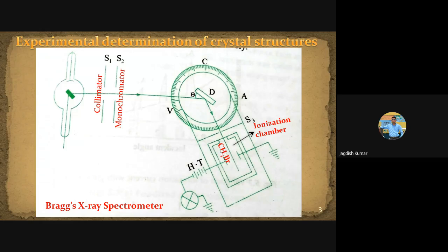So you will have CH3 plus ions and bromine negative ions, and because of this, the conductivity changes. Here, some high voltage is applied across the chamber. These are electrodes, cathode and anode. Then there will be an increase in current accordingly. So whenever there are high intensity X-rays, there will be high conductivity, and accordingly you will notice a high current in the ammeter. So an ammeter is employed. That is how we can measure the intensity of scattered X-rays with the help of this ionization chamber.